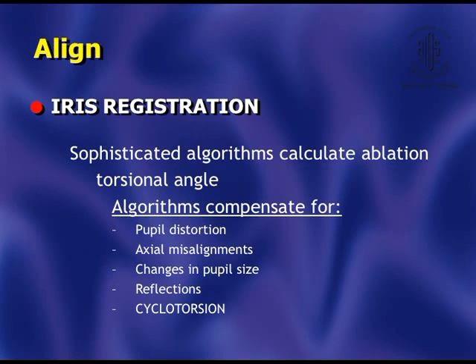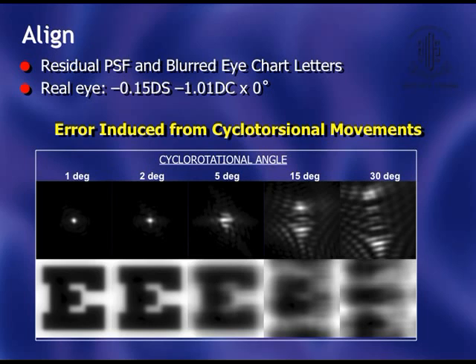Having created a shape to be formed on the cornea, the responsibility is that we need to create it exactly on the cornea. For this, you need to have not only an eye tracker but iris registration as well, because iris registration will compensate for cyclotorsion and will also compensate for the pupil centroid shift. The pupil changes when the patient lies down under the machine because of the intensity of the light, and because of the change in the pupil shape or size, the pupil centroid also shifts. Therefore, the responsibility of the machine is to center the ablation exactly over the pupil centroid. We all know that cyclotorsion is a reality, and if cyclotorsion is not taken into consideration, every degree of cyclotorsion will induce an amount of higher order aberration.